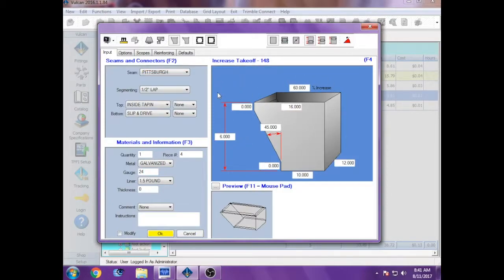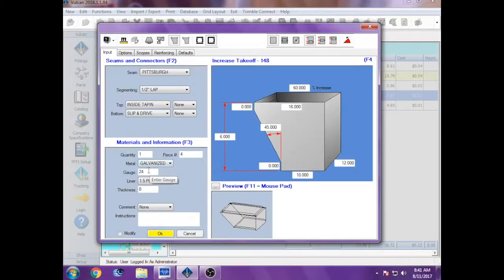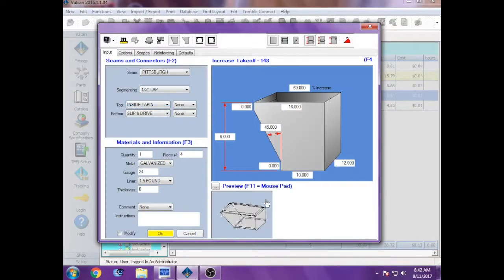You can leave all this stuff as it is unless there's something special, like maybe it has to be four inches long instead of six. But this stuff in here will automatically adjust to that. 24 gauge to keep it all in one piece of metal. Inside tap in is a tap edge, that's what this is here. Don't really ever change that, and this can be changed to flanges and stuff as needed. You hit okay.